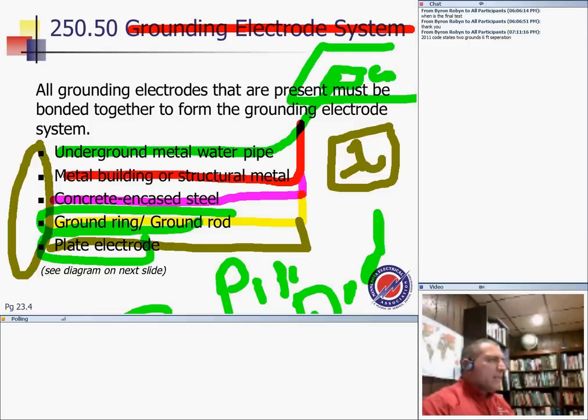That's why in residential, most of the time, all the time, we end up with a rod and pipe, right? Because that's the most common in Minnesota and a lot of states. This is the most common electrode that we have in a dwelling unit. It is a rod because we can drive a rod, and a pipe because we need water. Most of the time, metallic water coming to you, and they're changing now. But if it's water coming to you, then you can tie to them. That's why it's two, because one supplements the other.